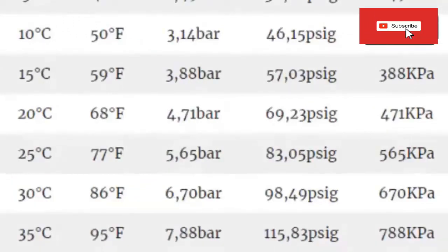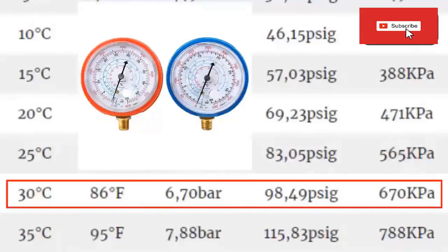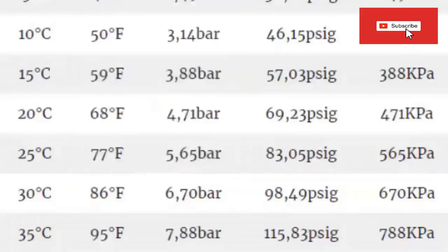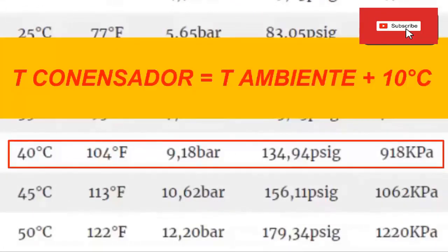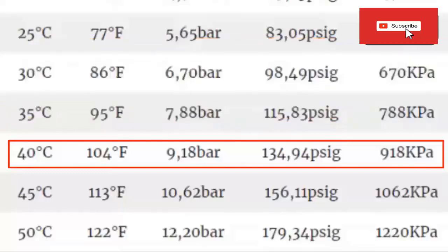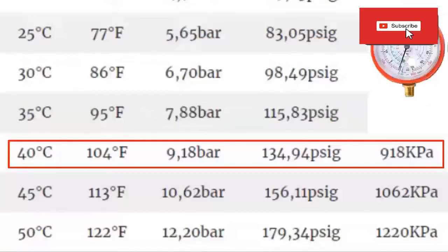In some cases it is useful to know the pressure of the equipment when it is turned off in the high pressure side or the condenser. For an outdoor environment temperature of 30 degrees Celsius, the equipment at turn-off has a manometric pressure, both high and low, of 6.70 bar, equivalent to 98.49 PSIG or 670 kilopascals. For an outdoor environment temperature of 30 degrees Celsius, the condenser temperature is usually about 10 degrees Celsius above the environment, so for 40 degrees Celsius, about 104 degrees Fahrenheit, the high gauge pressure in the condenser is 9.18 bar, equivalent to 134.94 PSIG or 918 kilopascals.